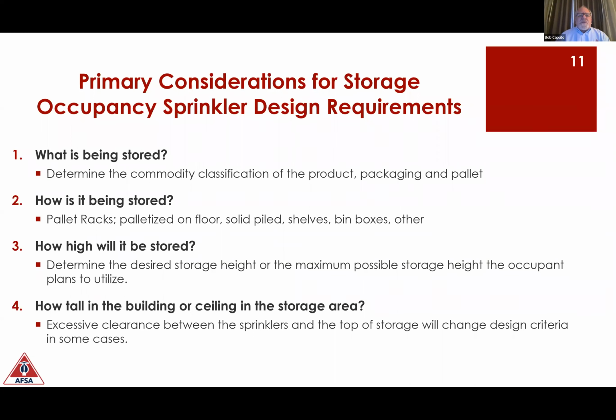Regardless, the primary considerations for the protection of storage occupancies are these four things. What are they storing? What's the commodity classification based on the NFPA 13 standard? How is it packaged and what kind of pallets do they have? Because the total of the heat that will be produced by a fire impacts not only the product, but the packaging and pallets, which can be metal, wood, or plastic. Plastics give the most amount of heat.